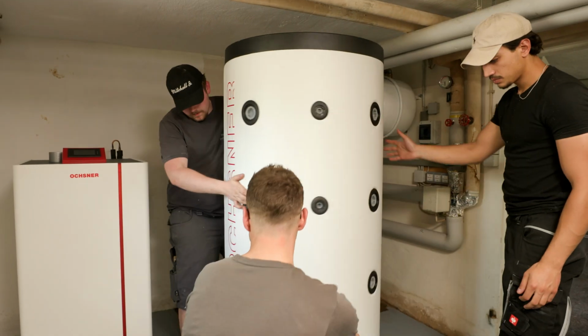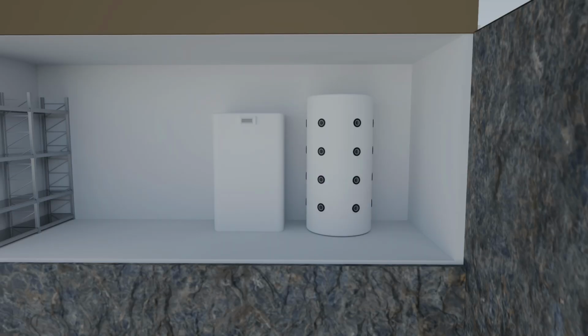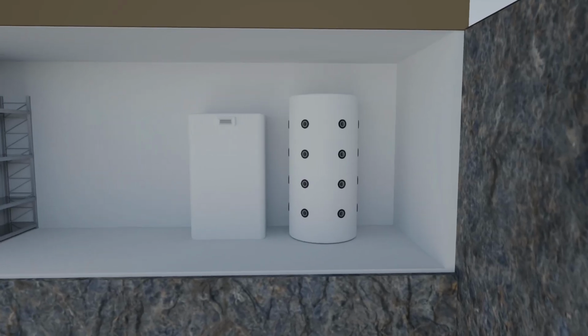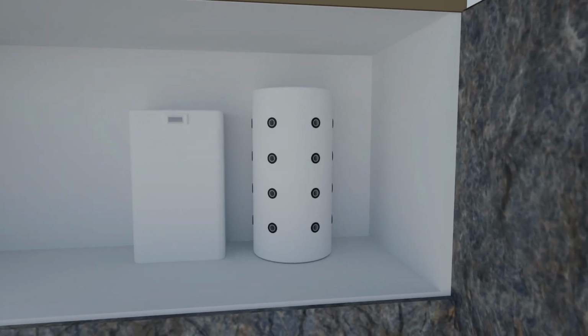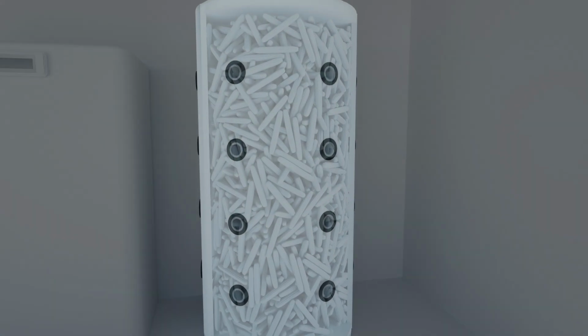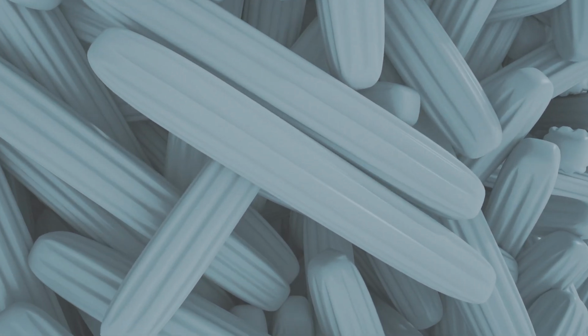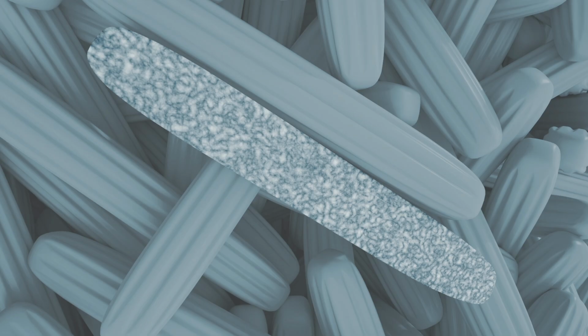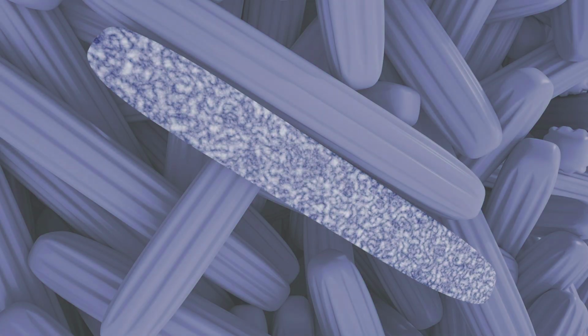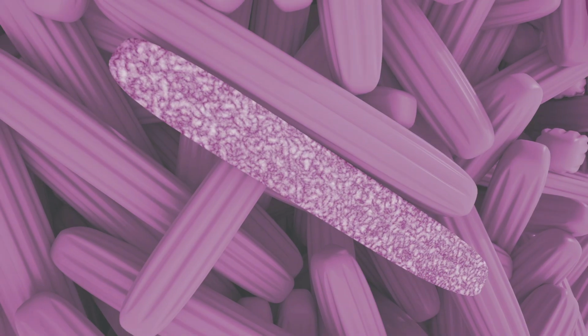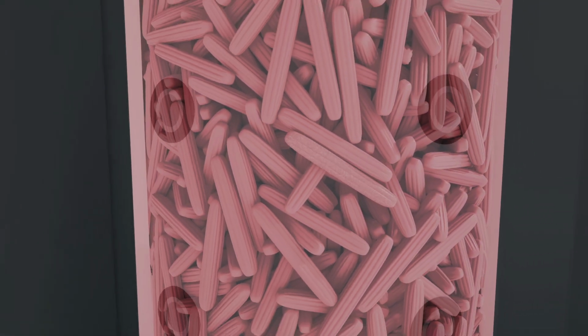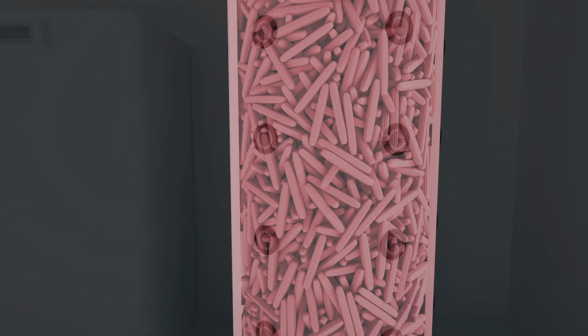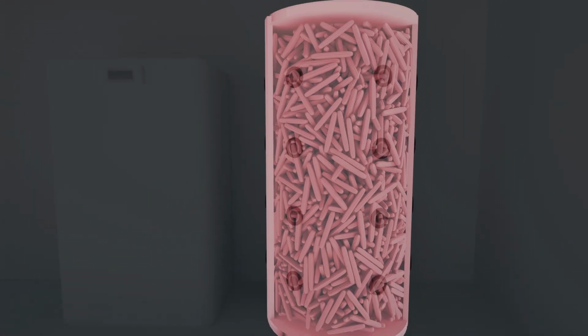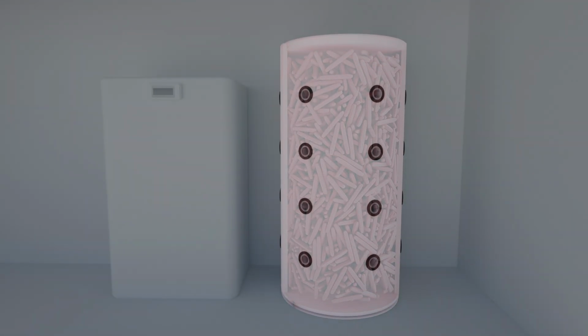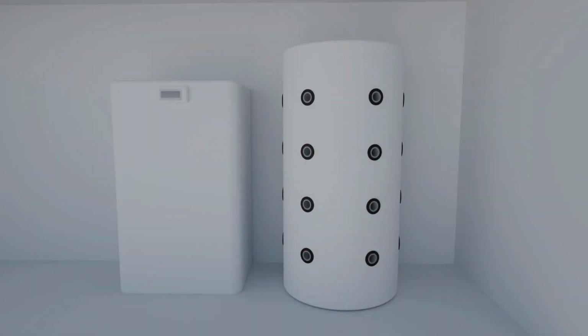And the volume of storage can be increased with a simple trick. Specially fitted plastic containers are placed into the buffer tanks. The containers are filled with particular kinds of salts or oils. These substances change their aggregate state from solid to liquid as the temperature increases, for example, at 50 degrees Celsius. During this change of the aggregate state, the material absorbs a much greater amount of heat energy than the same amount of water would absorb. Which means that a 1,000-liter storage tank suddenly has the heat storage capacity of around 2,500 liters.